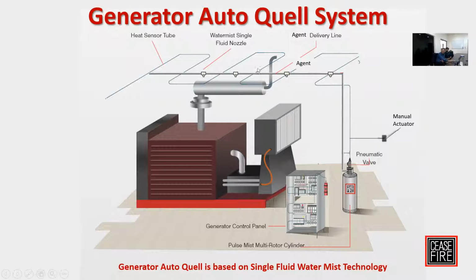This tube is the heat sensing tube, which is installed at the roof inside the canopy. Now, when a fire reaches this place, it ruptures the tube, and the indirect valve, which is installed over the extinguishing agent cylinder, gets actuated. The flow of the pulsated, bubbled water starts coming from here and going to all these nozzles, which are strategically placed in your genset canopy. It starts dispersing the water mist inside the canopy, thus quenching the fire immediately. That is the working principle of this.